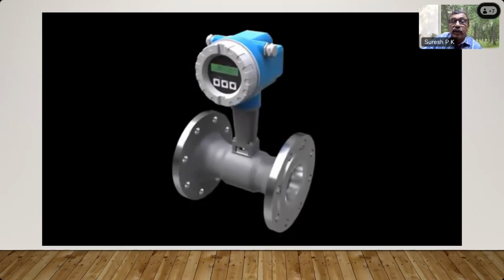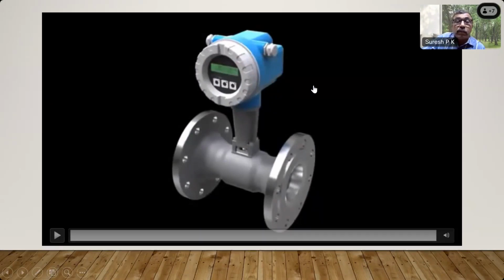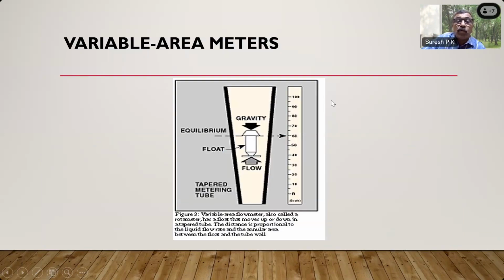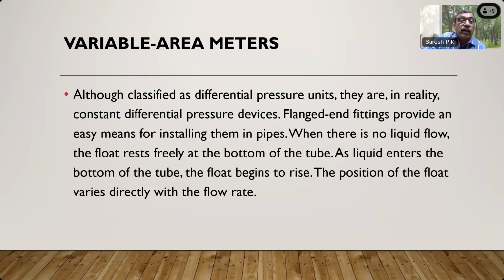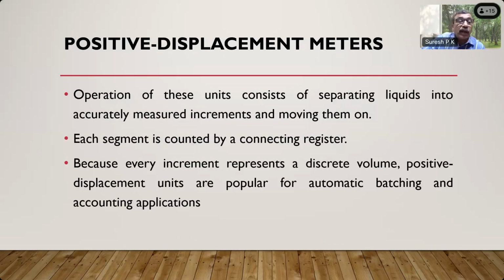Saturated steam it is applied, gases it is applied. So vortex meter is a popular meter in saturated steam and gas application. Now, this is a rotameter, which is very commonly used meter and not very accurate. This just gives an indication of flow rate. This is differential pressure, but accuracy is not as good as one would like to have.